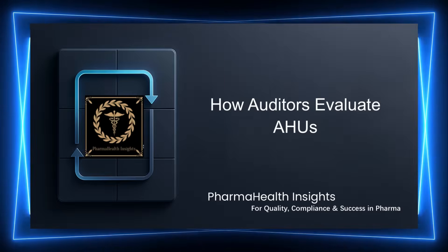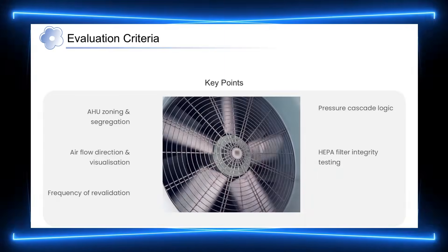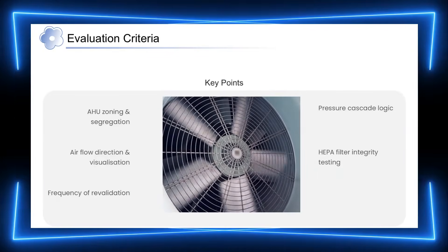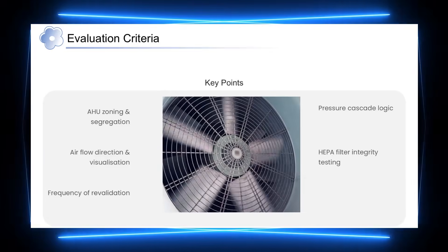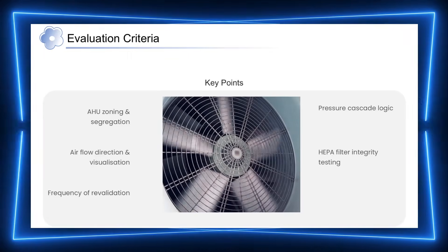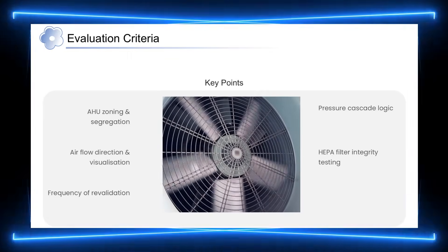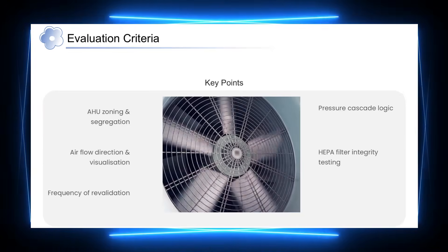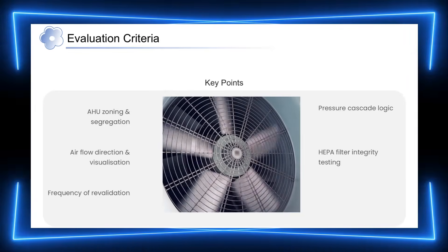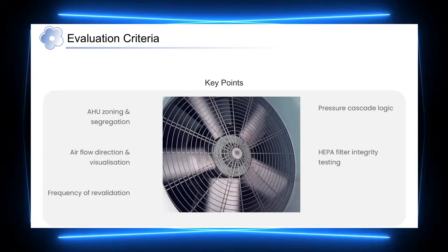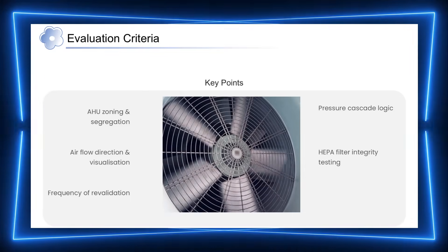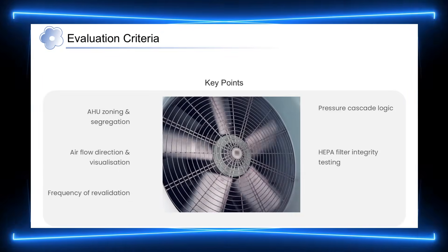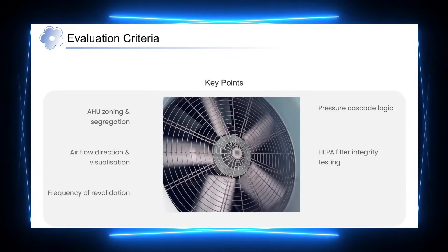This difference becomes crystal clear during audits. Inspectors evaluate AHUs through a risk-based approach. Their primary concern is whether the AHU design and operation can consistently prevent contamination and maintain controlled conditions. They closely examine how AHUs are zoned, how pressure differentials are maintained between areas, and whether airflow moves in the intended direction. Filter integrity, especially HEPA filters, and the frequency of revalidation are also key focus areas. Overall, auditors are not looking for complexity, but for clear logic, consistent control, and effective risk management.